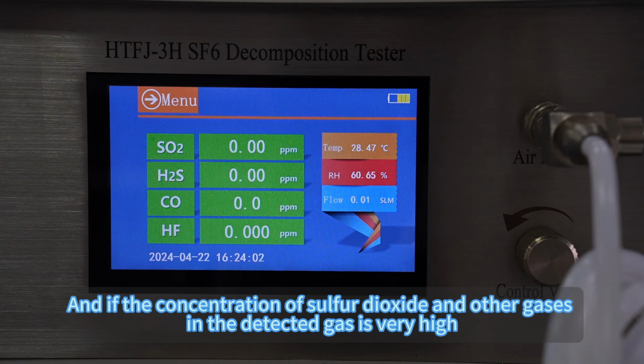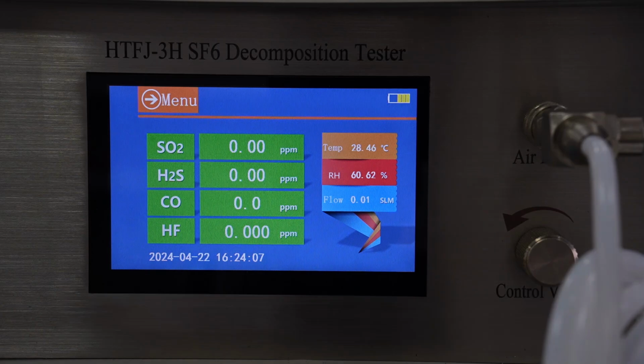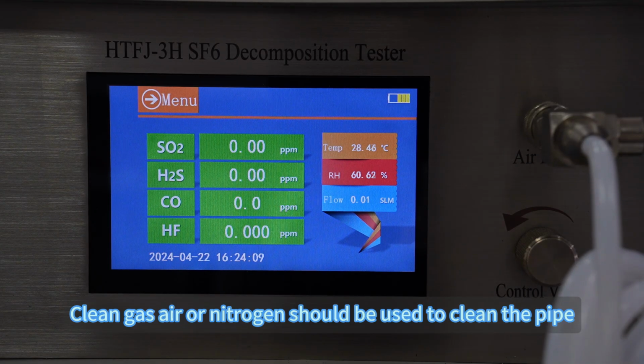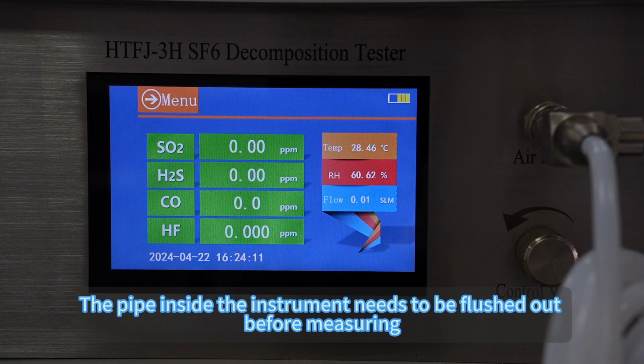And if the concentration of sulfur dioxide and other gases in the detected gas is very high, clean gas, air or nitrogen should be used to clean the pipe. The pipe inside the instrument needs to be flushed out before measuring.